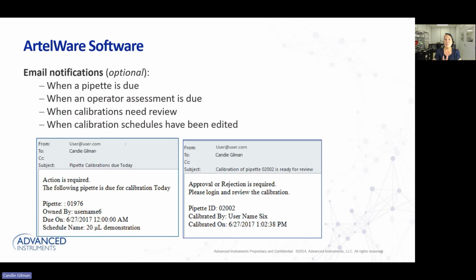And in addition, remember that optional email notification component of the software. This just gives you up close some examples of when those emails get sent out. So when pipettes are due or operator assessments are due, people will receive automated emails from the system. Anytime a calibration needs review, an automated email would go out as well, as well as for some other administrative functions that have been performed. So again, that's optional. You don't need to enable email functionality with the Artelware application, but you can. And it's pretty powerful when you combine that with a client server type of infrastructure when the software is installed.